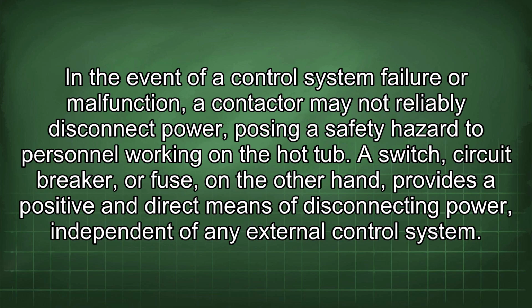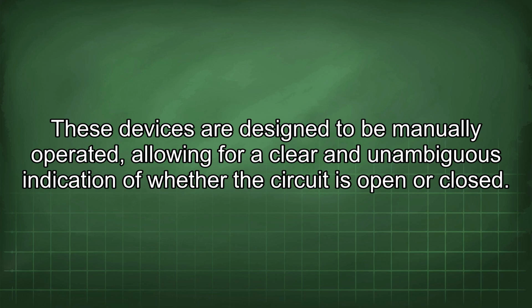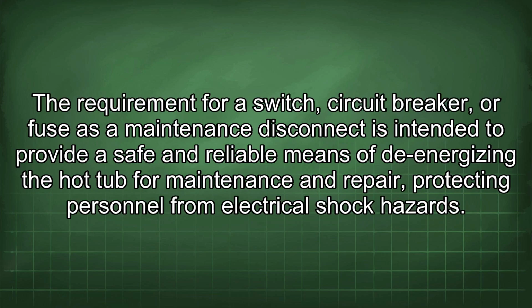A switch, circuit breaker, or fuse, on the other hand, provides a positive and direct means of disconnecting power independent of any external control system. These devices are designed to be manually operated, allowing for a clear and unambiguous indication of whether the circuit is open or closed. The requirement for a switch, circuit breaker, or fuse as a maintenance disconnect is intended to provide a safe and reliable means of de-energizing the hot tub for maintenance and repair, protecting personnel from electrical shock hazards.